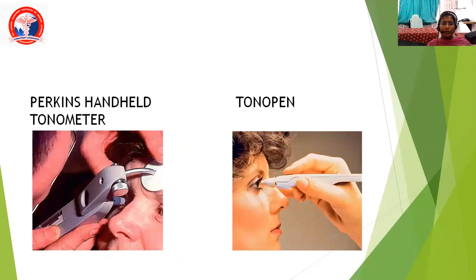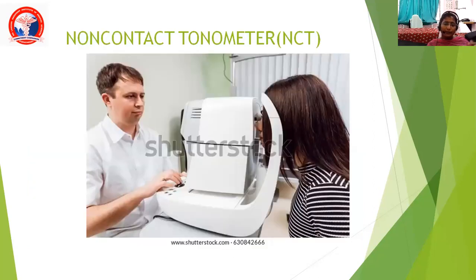The other tonometers are Perkins handheld tonometer and Tonopen. These are more recent. Perkins is usually used for children while measuring pressures in congenital glaucoma, also in examination under anesthesia in the operating theater. Since we are in the COVID era, we often go for the non-contact tonometer, which does not touch the patient's cornea. A puff of air is given and the pressure is recorded from the indentation it causes on the cornea. It is used mainly for screening; however, the gold standard remains the Goldmann Applanation Tonometer.